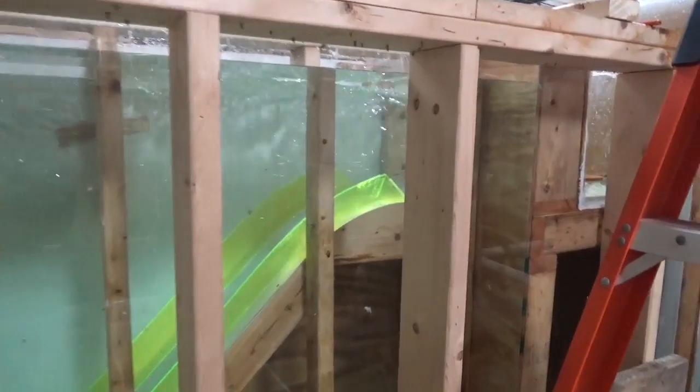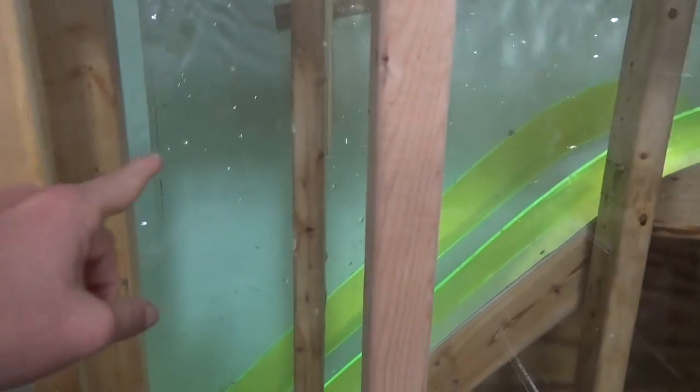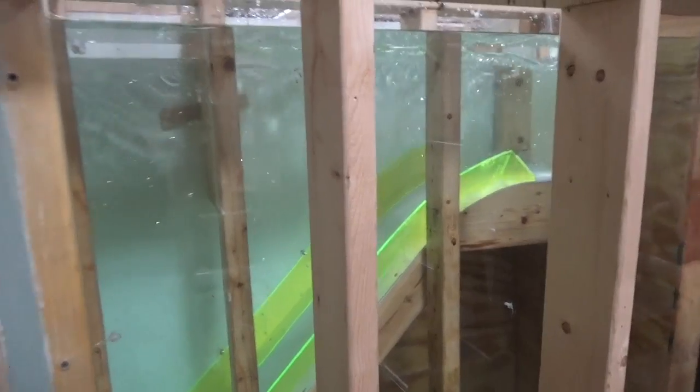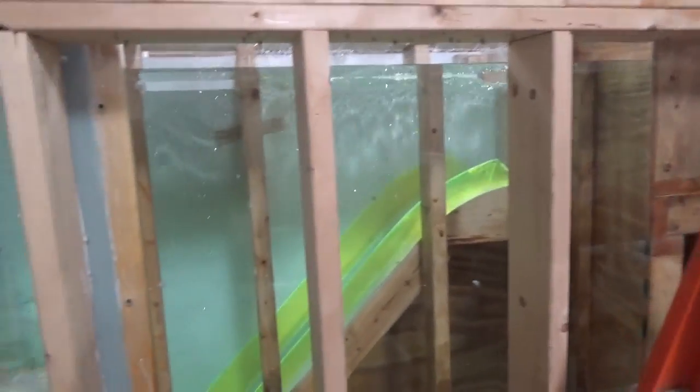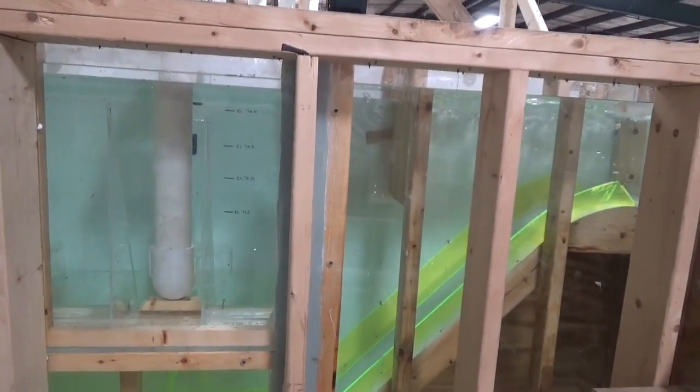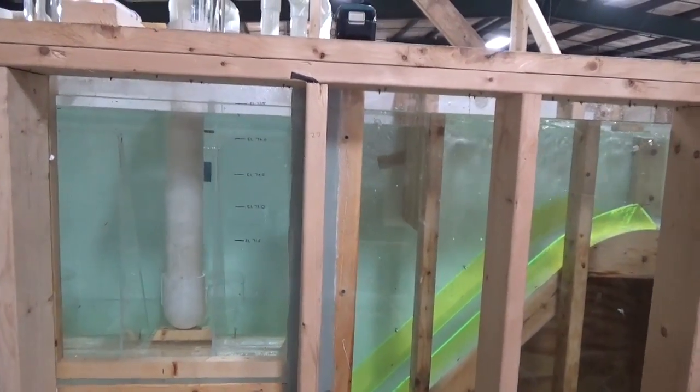Okay, so looking at 4 pumps now, we're going to note something here. Not very much air at all coming in right here. We see quite a bit at 76. So we've actually raised this up to 77. Sorry, I should have said that. It makes a big difference, that extra foot in here. So for 4-pump operation, we're going to note that if it's for any extended period of time, ideally it's going to be up at 77 rather than 76.